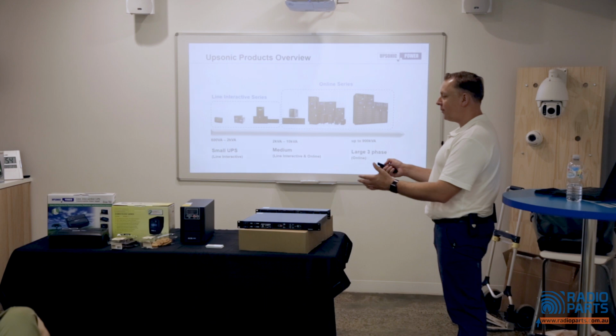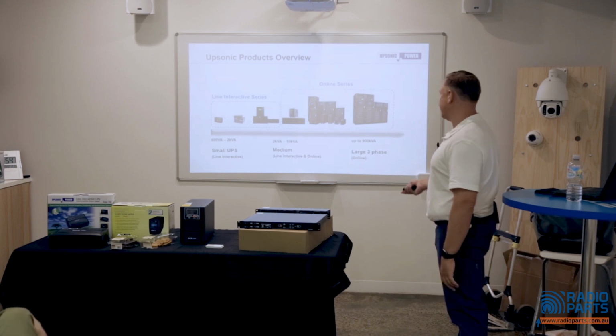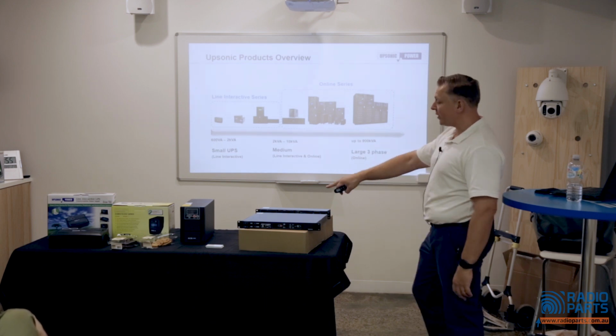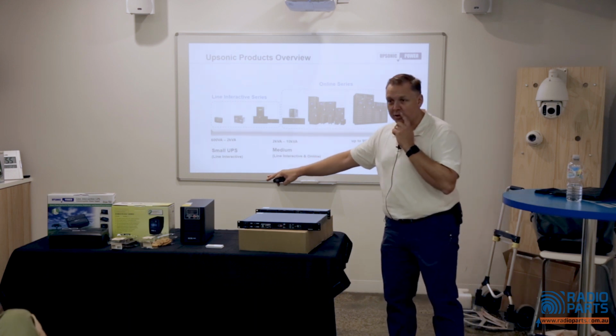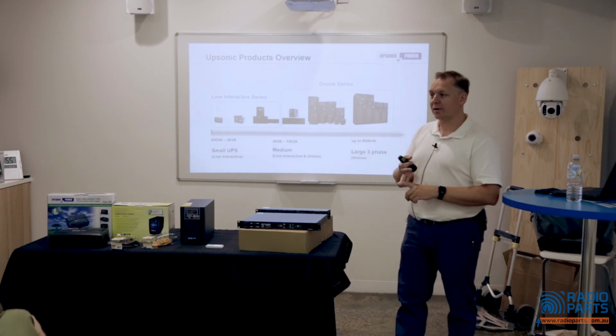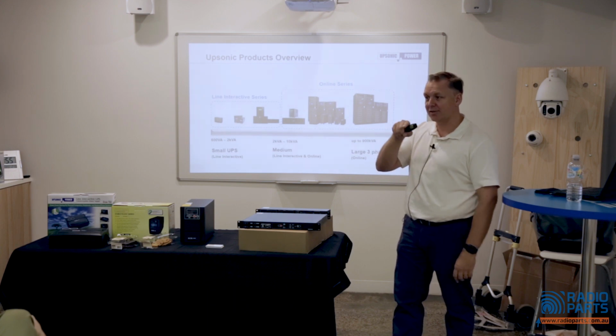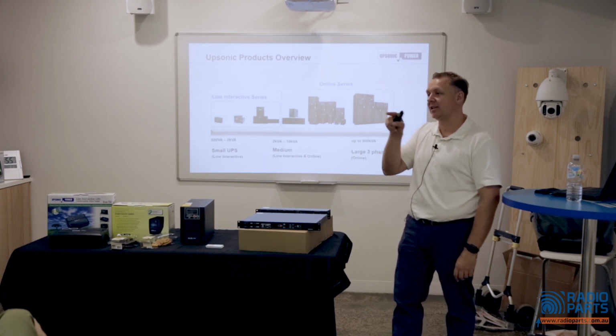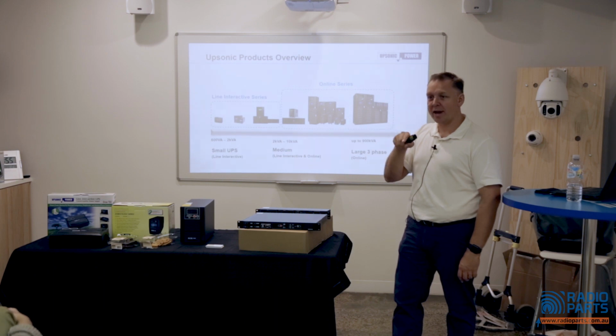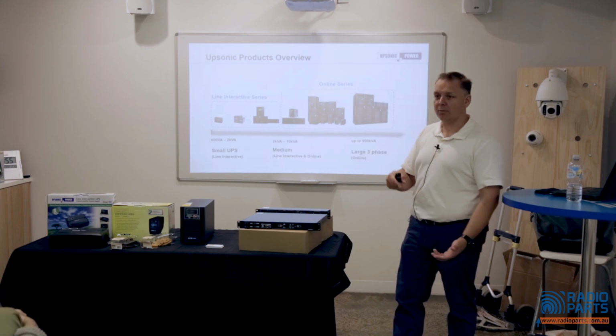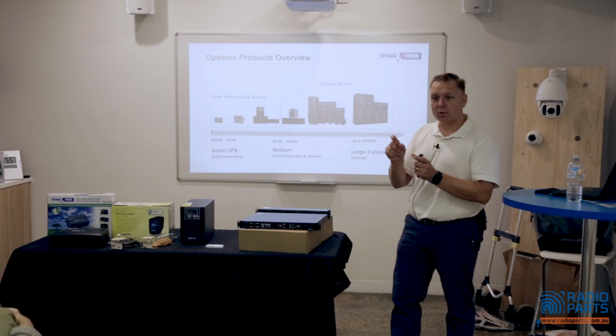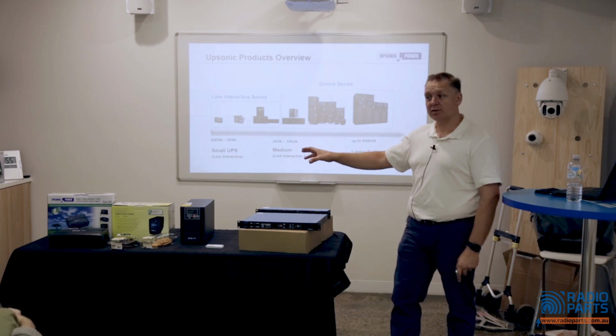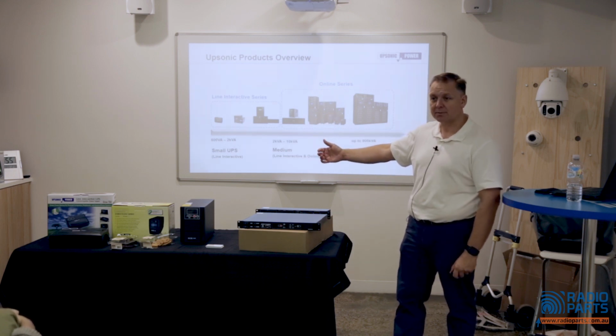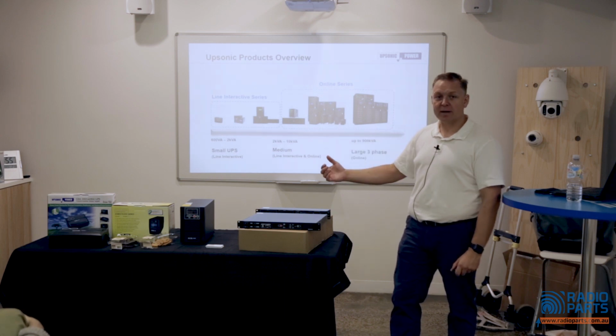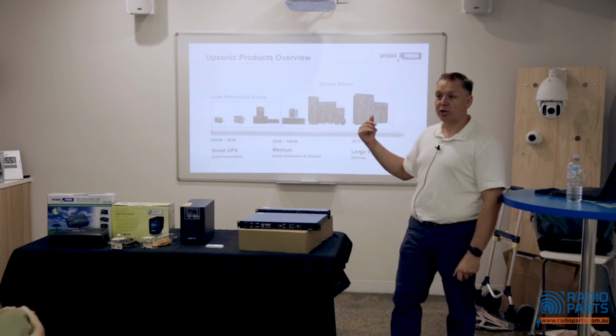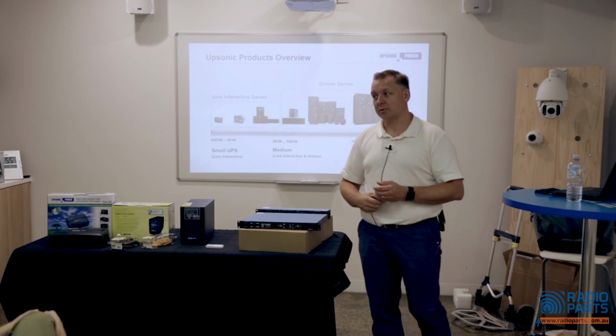Of course, they're still limited by the battery runtime as well. Just on that, while I'm mentioning it, with all of the pluggable units we have a long runtime and a short runtime. So a part number will end in S or ST for tower, or R for rack. The S and L are short runtime, long runtime. Short runtime has a smaller charger, has space for internal batteries, and you can go up to 2 external battery packs. Long runtime has no internal batteries because it has a bigger charger, and we can go up to 4 external battery packs on those.